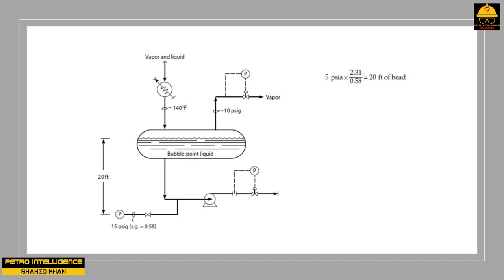The vapor pressure of the liquid also increases by 5 psi. This must happen because the liquid in the drum, which is in equilibrium with the vapor, is at its bubble point pressure. Since the available NPSH equals physical pressure at the suction minus vapor pressure of the liquid, if both pressures increase by 5 psi, the net gain in NPSH is zero.